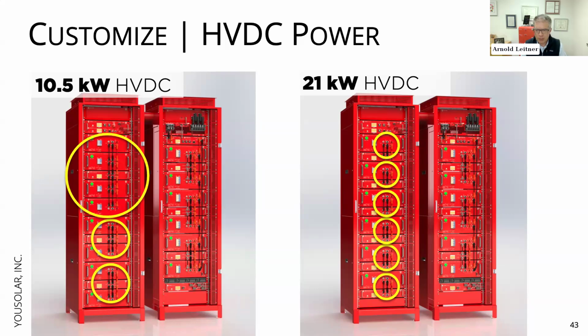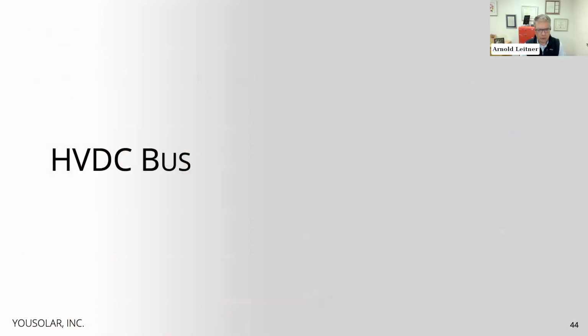You don't usually want to do this, and you usually don't need to do this. But if you wanted to, you can deliver 21 kilowatts of high voltage direct current power from the battery alone. Add up to 150 kilowatts or more of instantaneous solar power, and God forbid other energy sources, and you'll soon be exceeding whatever DC load you want to meet. Again, that is the virtue of the high voltage direct current bus.